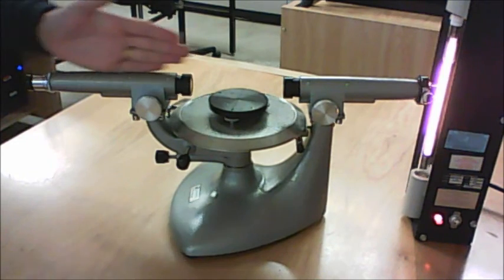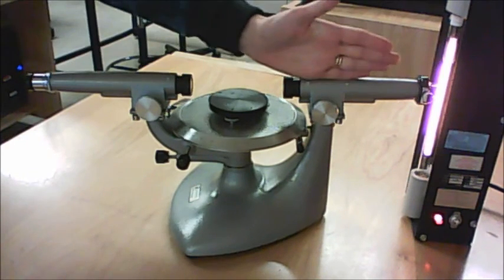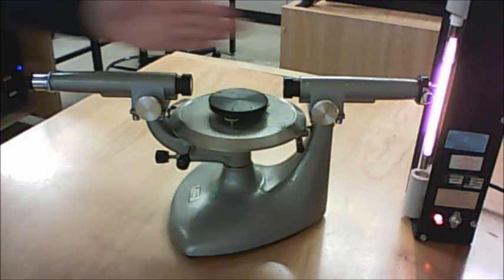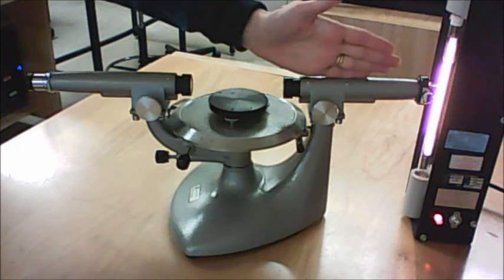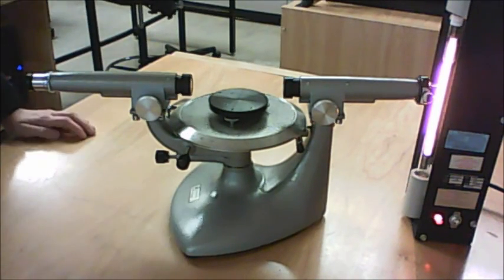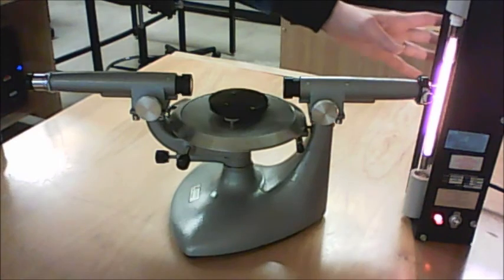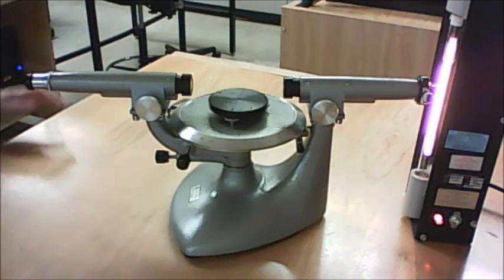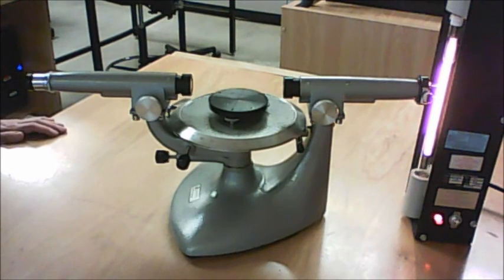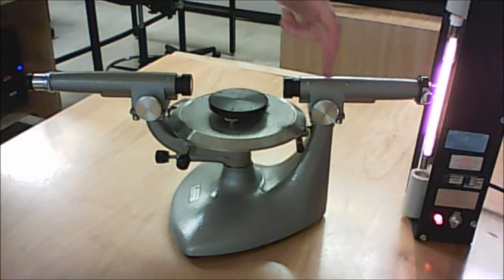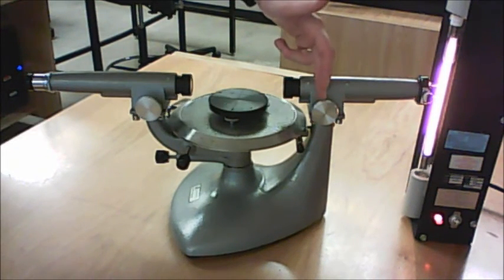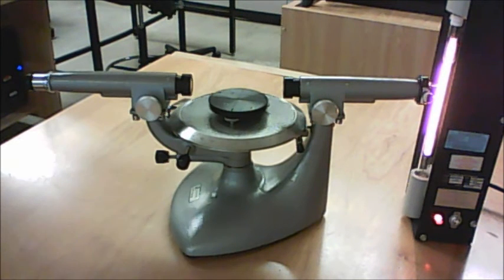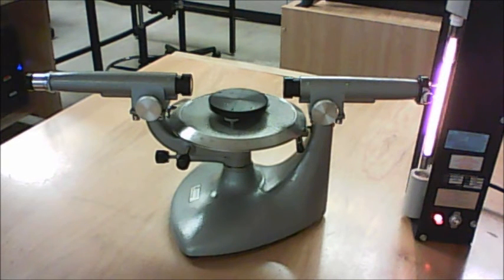And you want to look through the telescope with the telescope aligned with the collimator. So you're looking straight through towards the light source. Adjust your lamp back and forth so that the center line looks as bright as possible. And then you focus your collimator to make sure that that central line looks as in focus as possible.